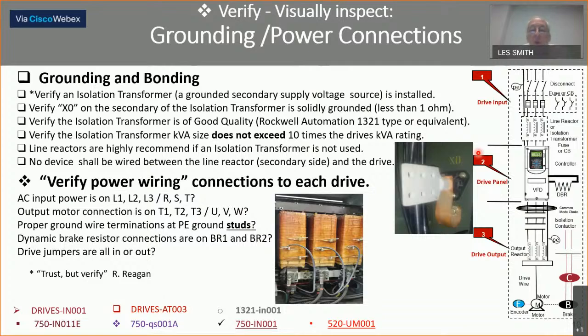Verify the isolation transformer is good quality. Sometimes transformers of lesser quality can give you more problems down the road, even on installation. I've had contractors that liked the beefier transformers for lifting, etc., because it was quicker to install as far as rigging. Verify the isolation transformer KVA does not exceed 10 times the KVA of the drive. This has to do with the amount of energy that drive will accept on power up. The 10 times rule is for your component drives, or drives that don't have an inductor between the converter and the inverter. Now, the automotive or architectural drives will have an inductor between the converter and inverter, and it can take 20 times the size of the transformer. We'll talk about this a little bit later.